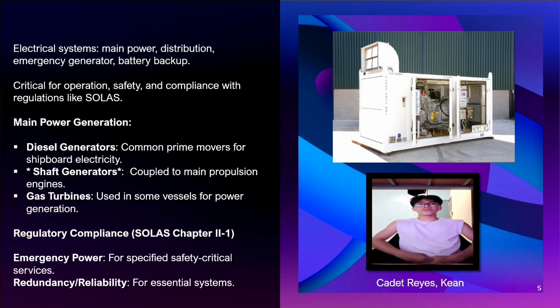The main power is responsible for supplying electricity to all major systems we need for normal operation, such as lighting, machines, communication systems, and even propulsion in the case of a ship. Without a stable main power supply, day-to-day operation would not be possible. Next, we have the power distribution system. Think of this like the veins in the human body that carry blood. The distribution system takes the electricity from the main power source and delivers it to the different parts of the facility. This is done through switchboards, transformers, circuit breakers, and cables.